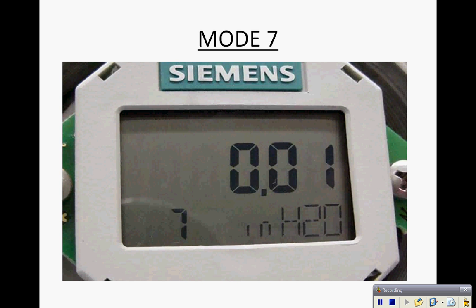Mode 7 is where we would set the zero for the mounting position. We can zero the transmitter out this way by holding the span and zero buttons down on the transmitter until it reads zero.